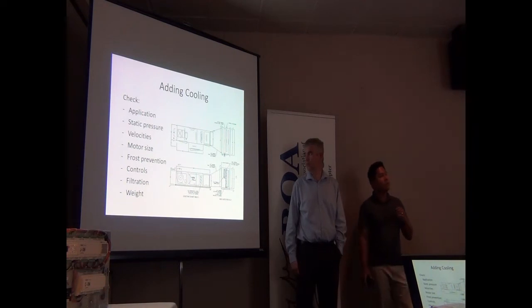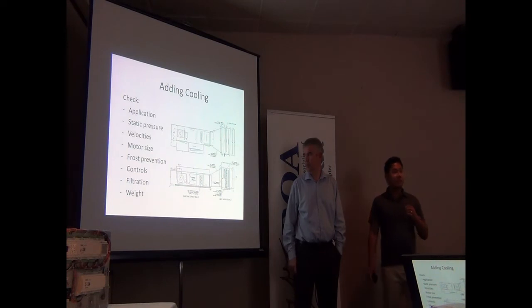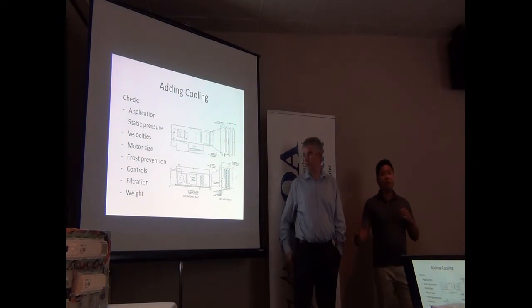If it's makeup air, what happens in the heating season when you're not using cooling? You have to consider frost protection, you don't want to freeze up that coil and clog your airflow. Look at the existing controls versus the new controls you're putting in, and how you can tie into the existing controls to make it work. And again, you add filtration, and of course the weight, can the roof or wherever you're mounting it handle the additional weight?